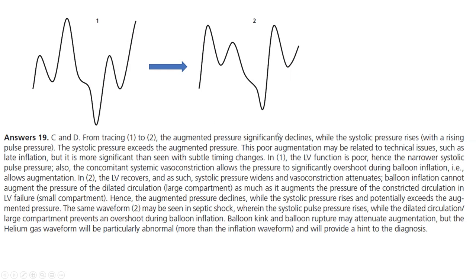So here the augmented pressure significantly declines while the systolic pressure rises with a rising pulse pressure. In this case, even the assisted systolic pressure exceeds the augmented pressure. This poor augmentation may be related to technical issues such as timing of inflation, but it is more significant than what we see with subtle timing changes. And nowadays, the machine does all the adjustment of timing. The machine is very smart, so you're not going to get that dramatic poor augmentation from those subtle timing changes.